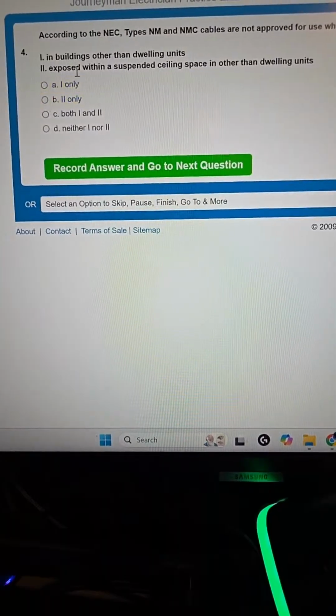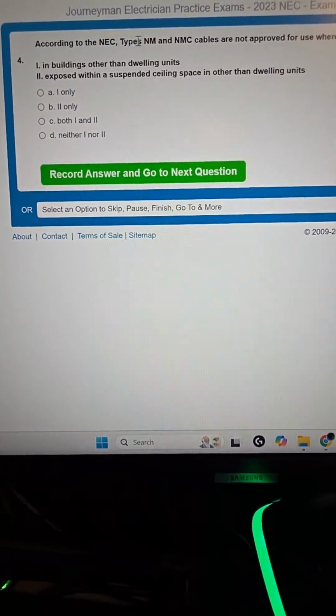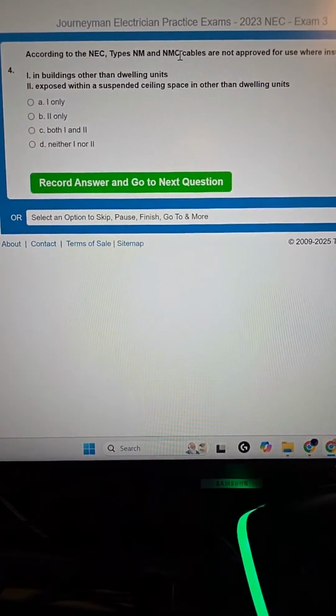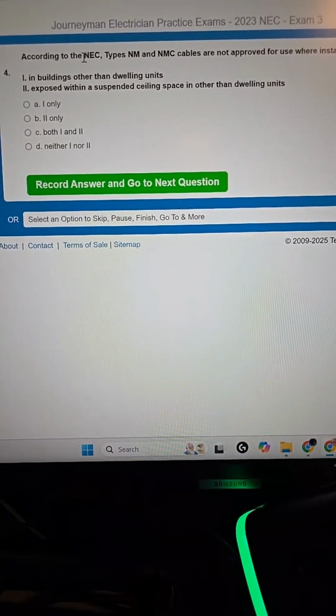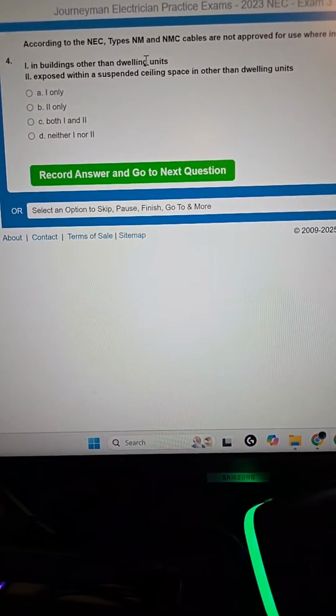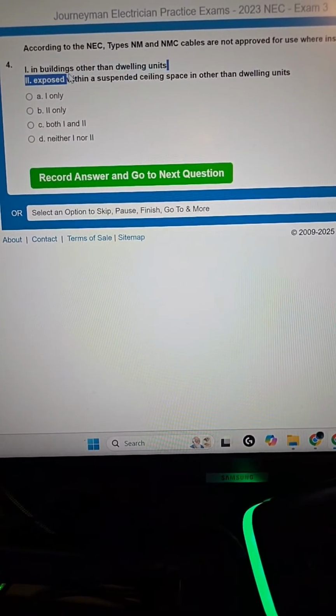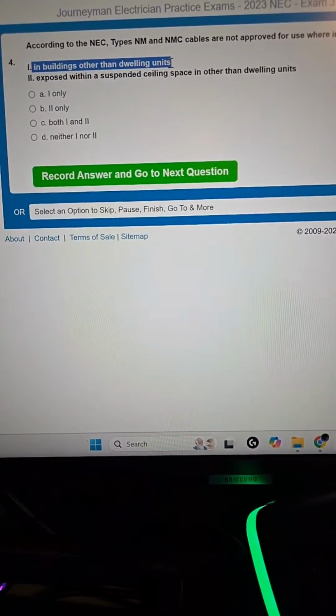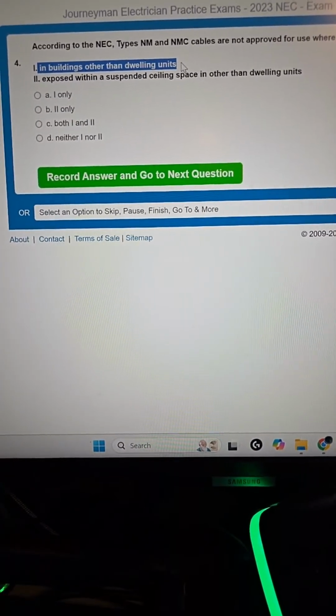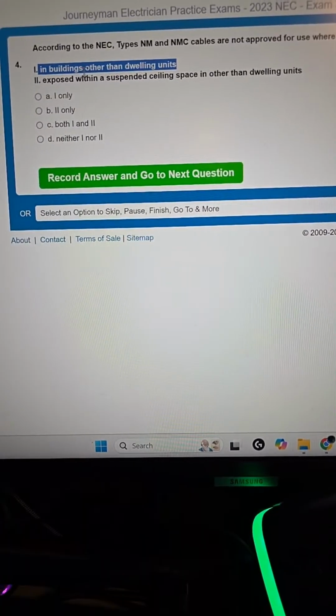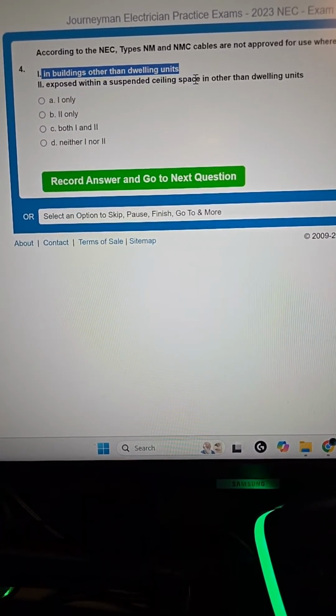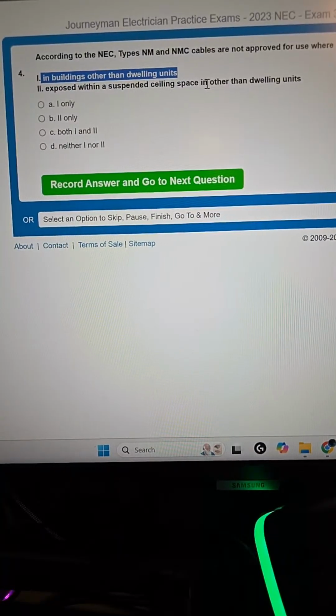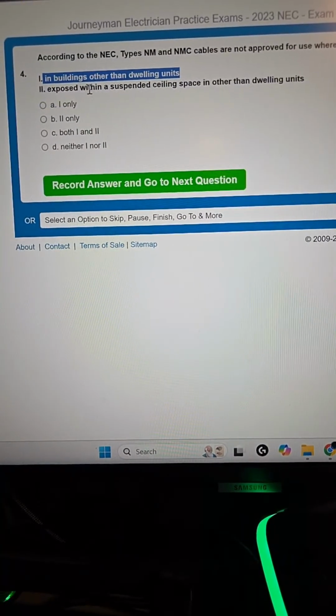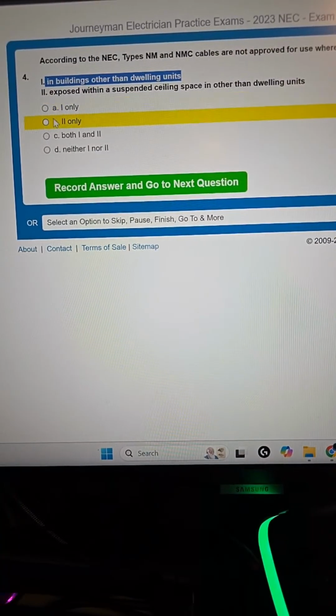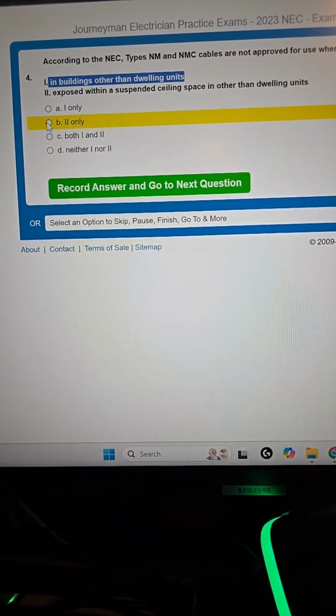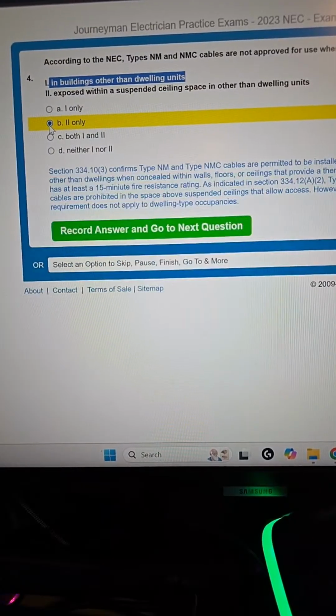So, in buildings other than dwelling units, NM is Romex. NMC is also Romex. So, what we know about Romex is that it can be in dwelling units, and it can also be in commercial buildings. It just can't be within a suspended ceiling space. So it's going to be just 2. This one. Yeah, we got it.